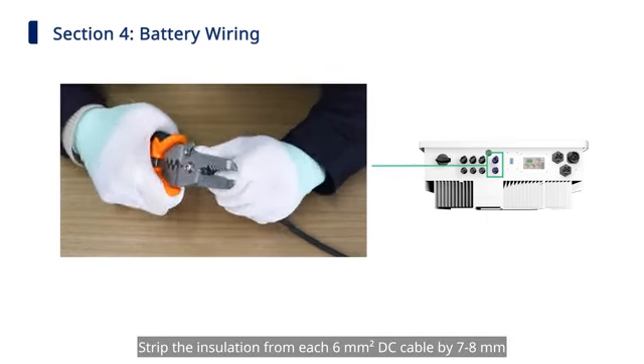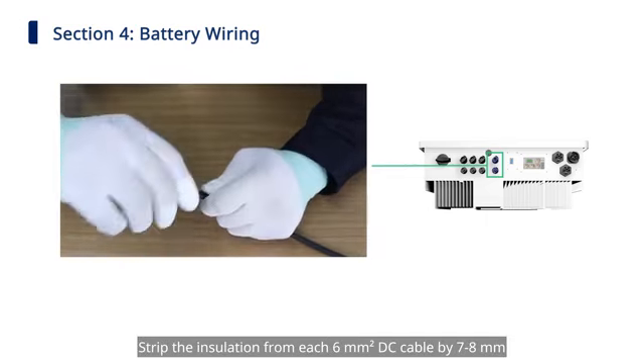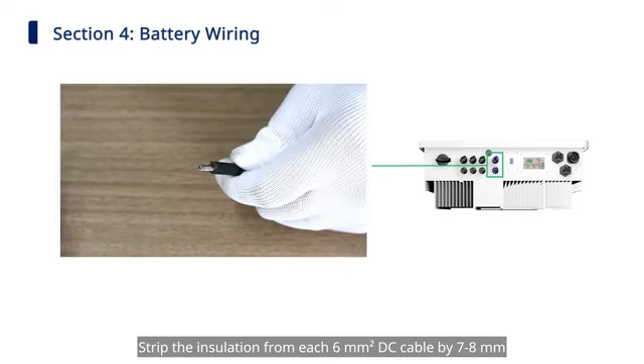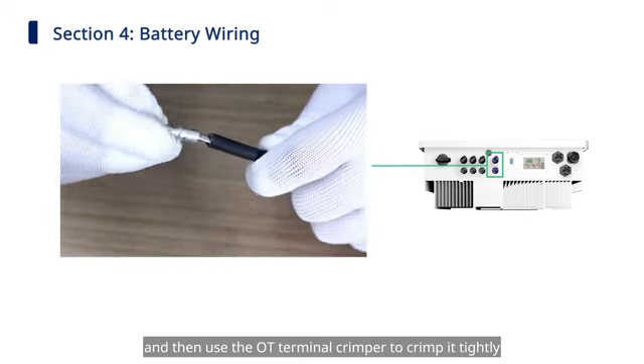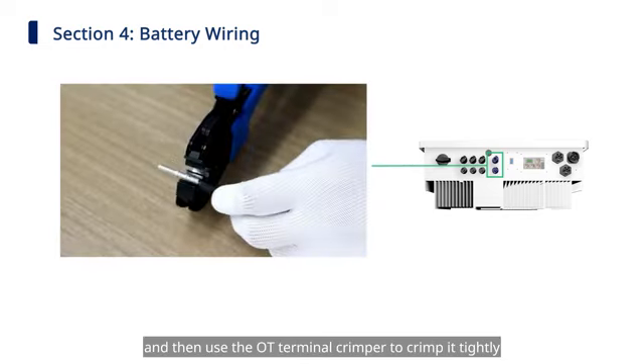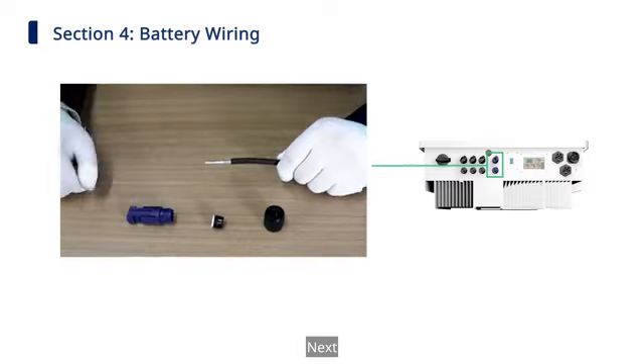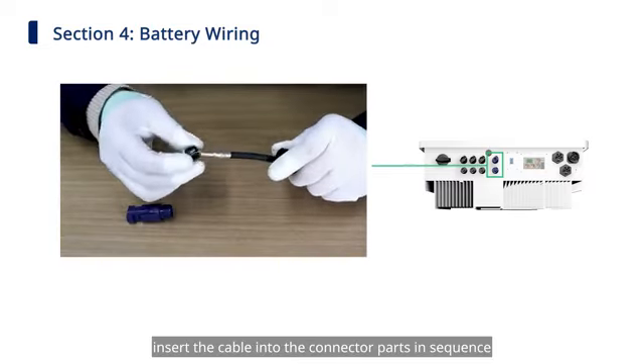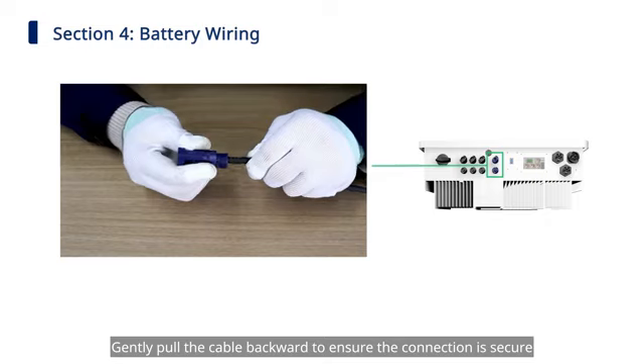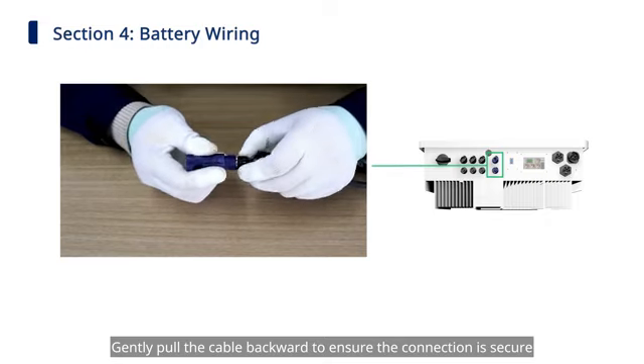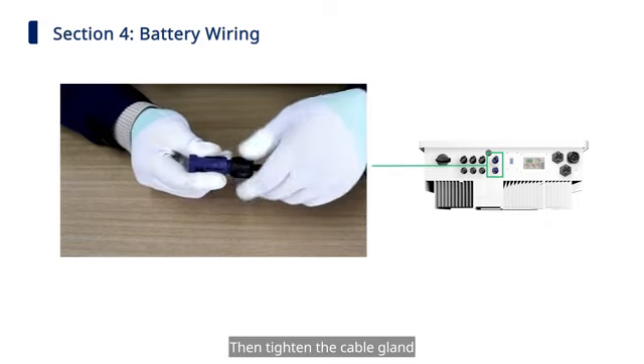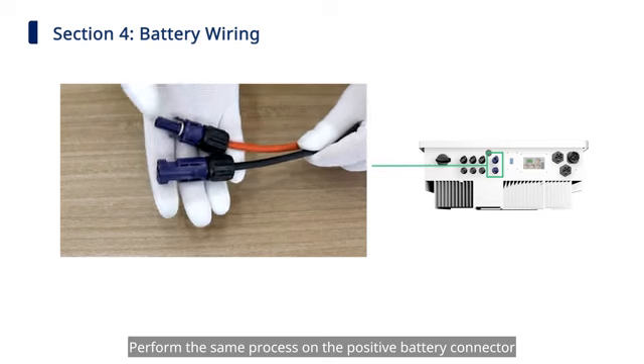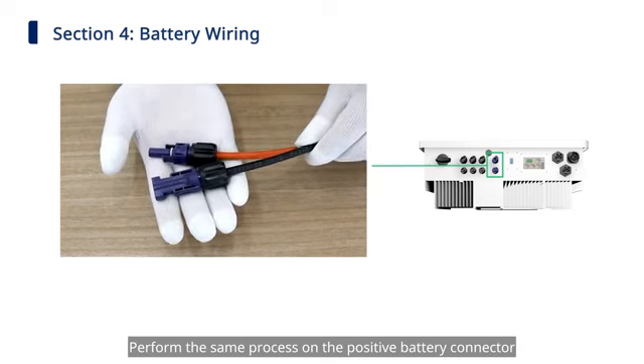Strip the insulation from each 6 square millimeter DC cable by 7 to 8 millimeter, and then use the OT terminal crimper to crimp it tightly. Next, insert the cable into the connector parts in sequence. Gently pull the cable backward to ensure the connection is secure. Then tighten the cable gland. Perform the same process on the positive battery connector.